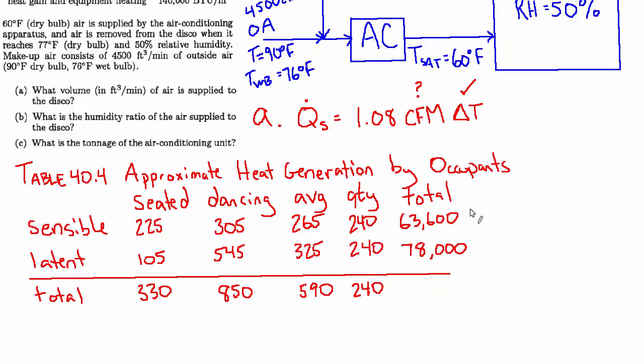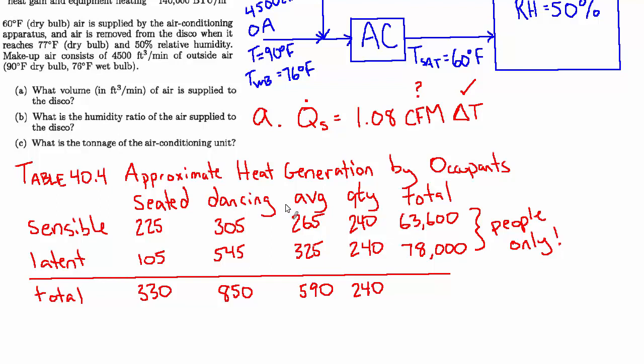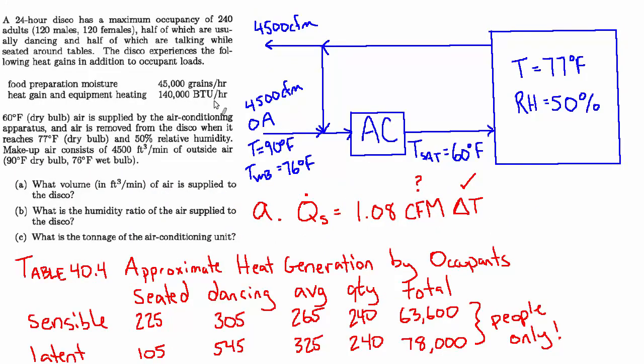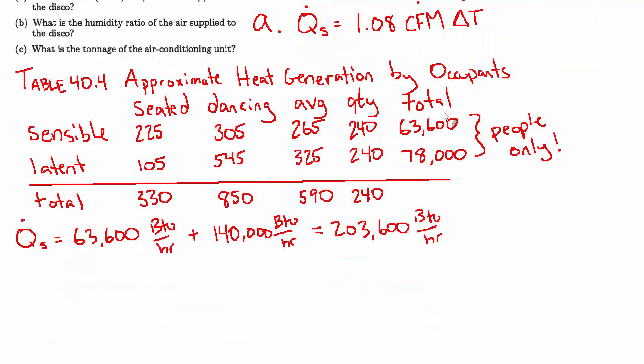Because we also have these latent and sensible contributions from food prep and other heat gain and equipment in the space, so we're going to have to include those. So for the moment, let's just tally up the sensible since that's what we care about for part A. We can say q dot s sensible heat load equals the 63,600 from the people plus this 140,000 BTUs per hour from the equipment. We don't need to worry about the food prep since that's latent, and that equals 203,600 BTUs per hour.